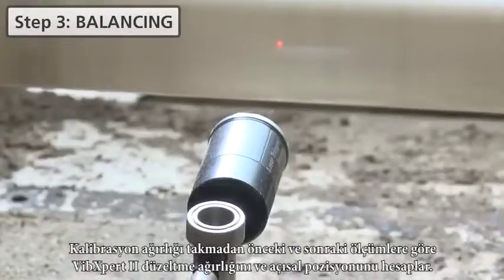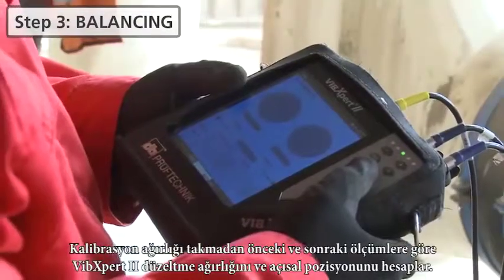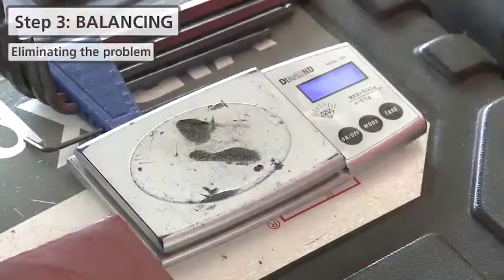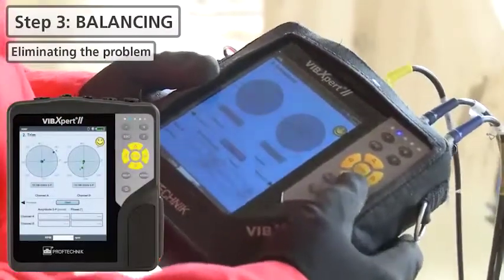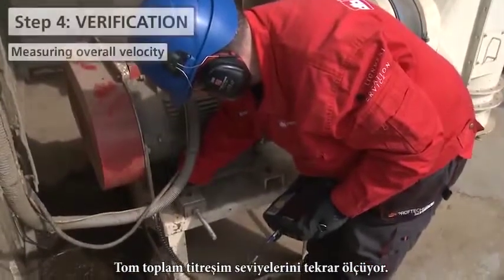Based on the measurements with and without trial weight, VibXpert II calculates the correction weight and its angular position. The weight is welded to the fan. Tom then measures the overall vibration level again.